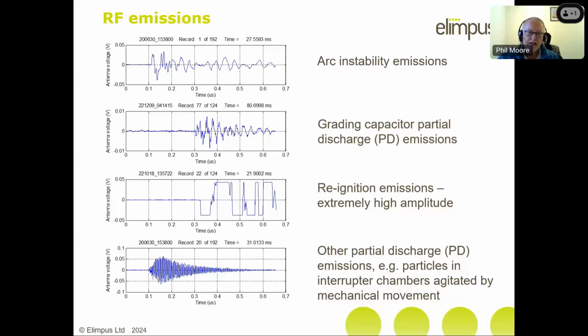And as a general rule, those RF emissions should be the same on all three phases. It might not be over one operation, but if you looked over 10 and you average the number of RF emissions, it might be, you know, between, I don't know, 3 and 12. It's that sort of level. It depends upon the manufacturer, design of the interrupter. The presence of arc instability emissions isn't really good or bad. They're just there. They're just the way that the thing works.